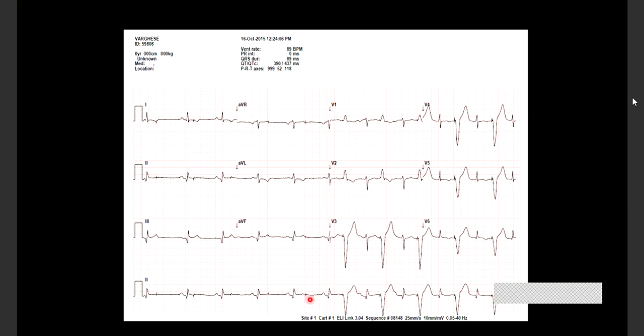I saw an answer on magnet. What will happen is, when you put a magnet on a pacemaker, it is true that it will go into an asynchronous mode, but it will go to a magnet rate, which is much faster than the set heart rate of 60. Earlier, not so commonly now, whenever a pacemaker patient came, you would put a magnet on it. What a magnet does is suspend intrinsic sensing activity. So there's no sensing. It goes into an asynchronous mode. But you will realize the magnet rate is much different from the set rate.